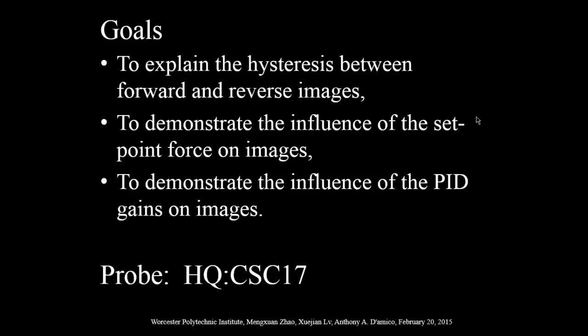You have several goals to achieve at this lab session: to explain the hysteresis between forward and reverse images, to demonstrate the influence of the setpoint force on images, and to demonstrate the influence of the PID gains on the images. The probe you use this time is the same as Instrument Lab 2. It is HQ CSC 17.